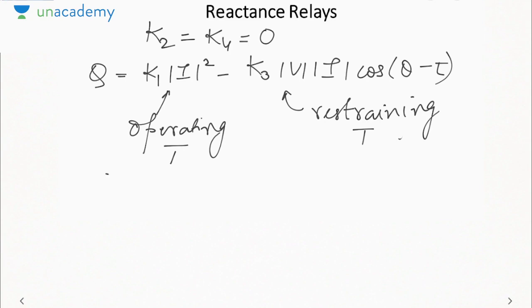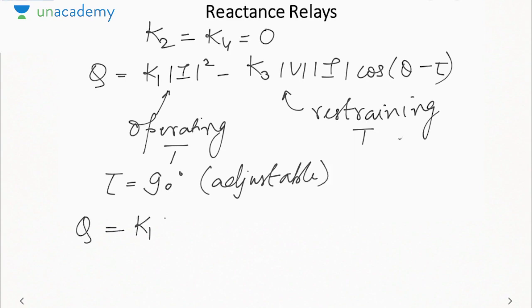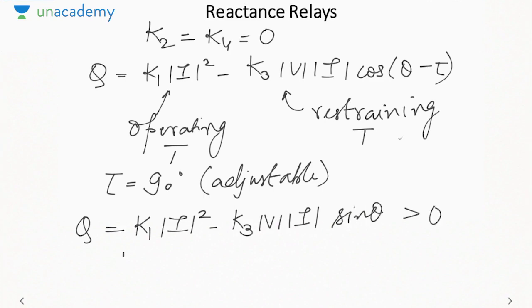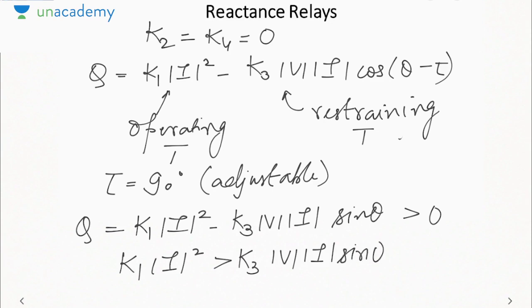Then what we will do is adjust tau to 90 degrees, because it is controlled by the user. It is adjustable, so we set tau equal to 90 degrees. That means Q is equal to K1 mod I square minus K3 mod V mod I cos of (theta minus 90), which is sin theta. This must be greater than 0. So K1 mod I square must be greater than K3 mod V mod I sin theta.